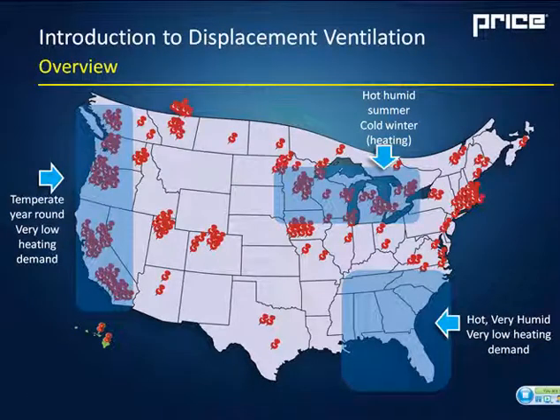So to give you an idea of the job distribution across North America, this is a distribution of our projects up until about early 2009. This slide was updated. So we have a very high concentration on the west coast simply because the climate is very temperate. They can take advantage of something called free cooling, which I'll get into a little bit later. Basically, the cooling demand is low, the humidity is low, so it favors warmer supply temperature, and they can be bringing in outdoor air or running their economizer for a lot more hours of the year.